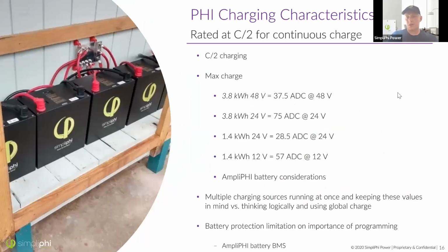As far as charging characteristics, our batteries are rated to charge and discharge at C/2. So really what this means is, the easiest way to do it is to take the amp hour capacity of the battery. You just divide that by 2, and that is the charge and discharge rate of that same battery. So for example, the 3.8 kilowatt hour 48 volt battery is a 75 amp hour capacity. You just divide 75 by 2 and you get 37.5 amps.